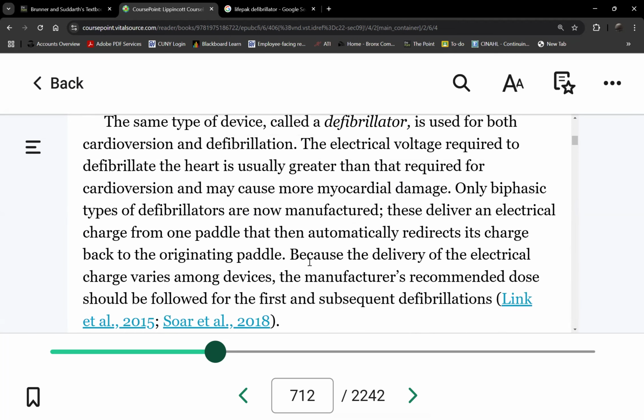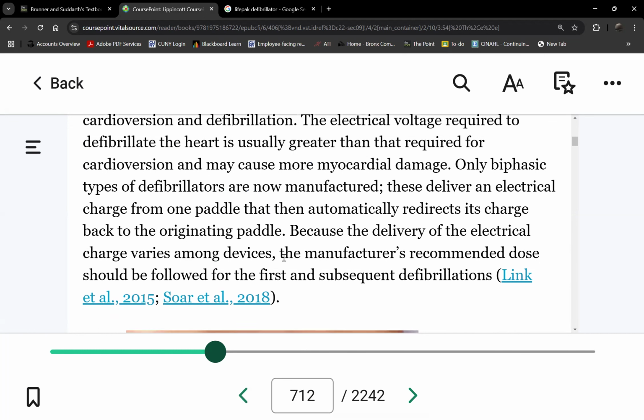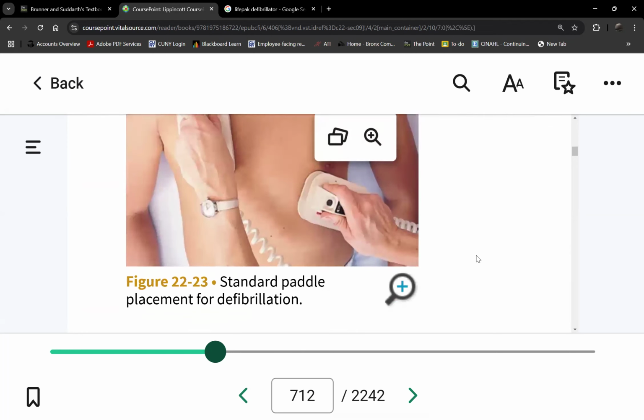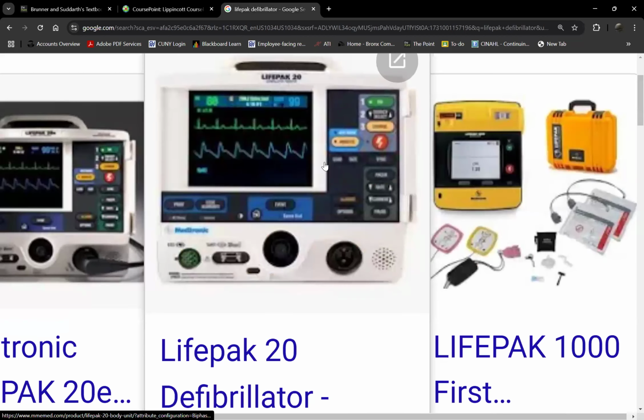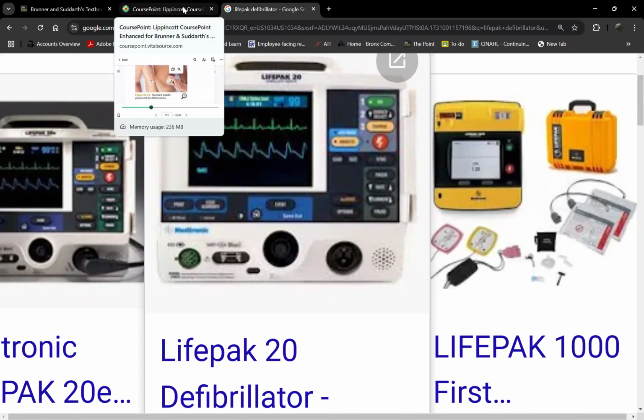Any questions on the difference between the two? The function is to give the shock, like every maybe 2 seconds it shocks, then shocks again, like pacing. That's a pacemaker. Yes, the same machine is also an external pacemaker, a temporary pacemaker. That's what you're asking, right? Yes, we can also use this as a pacemaker. A temporary pacemaker. I emphasize temporary, because are you going to live like that for the rest of your life, having electric shocks delivered constantly? No. This is only temporary, so a few hours.